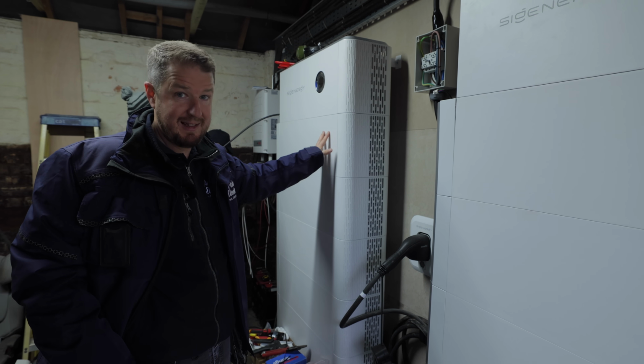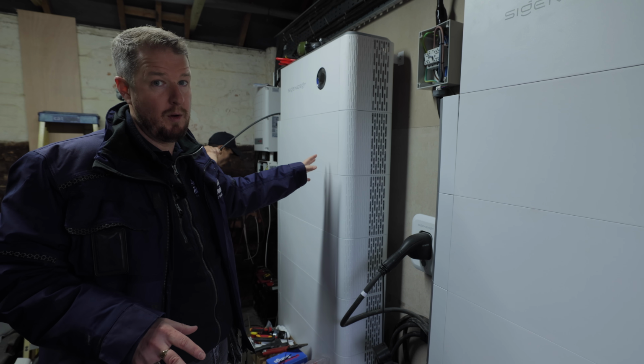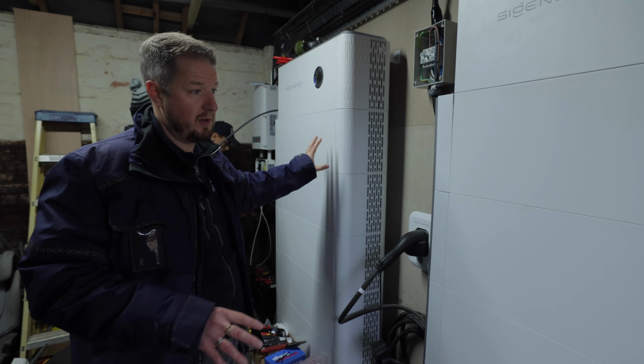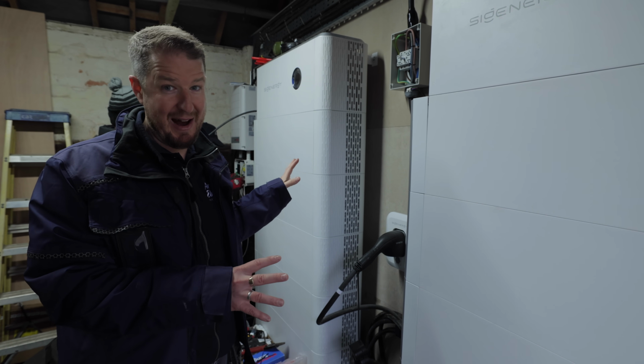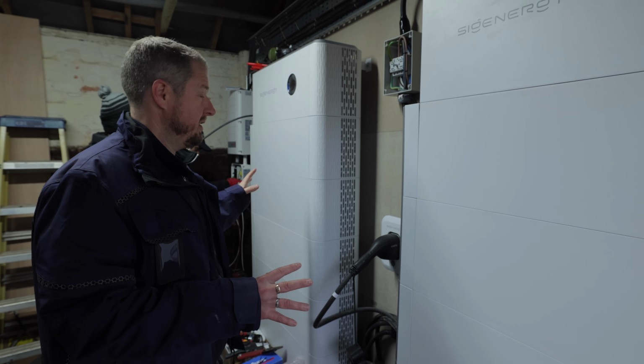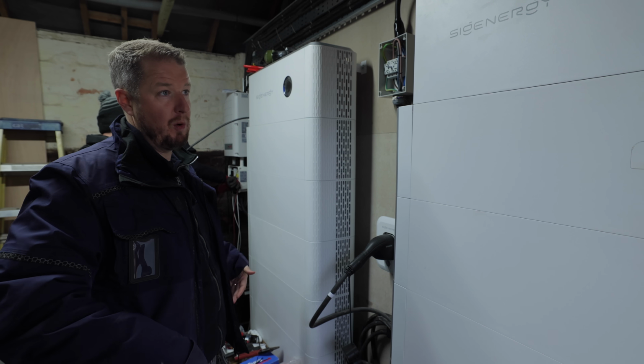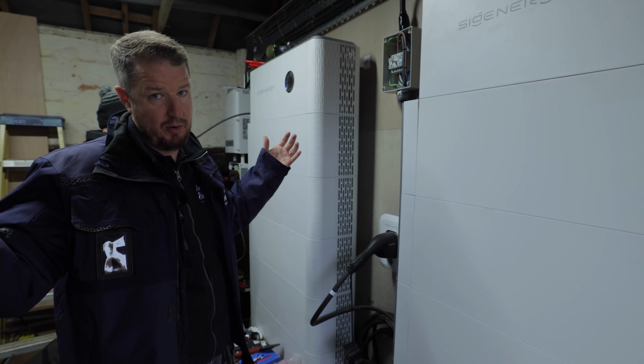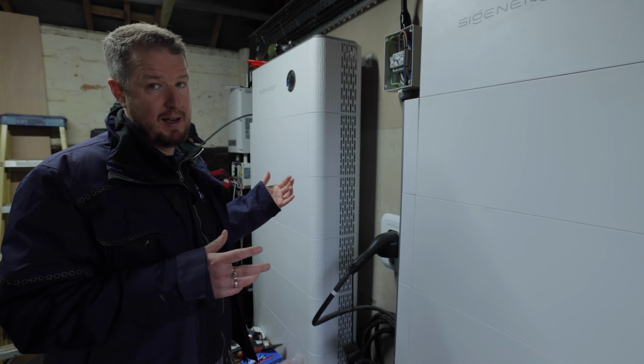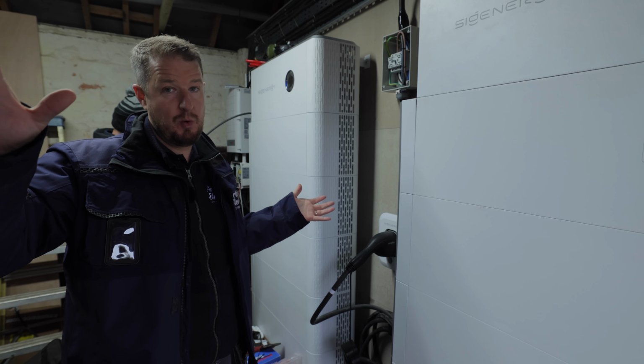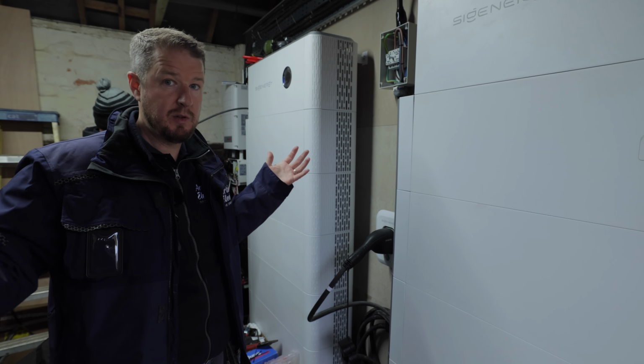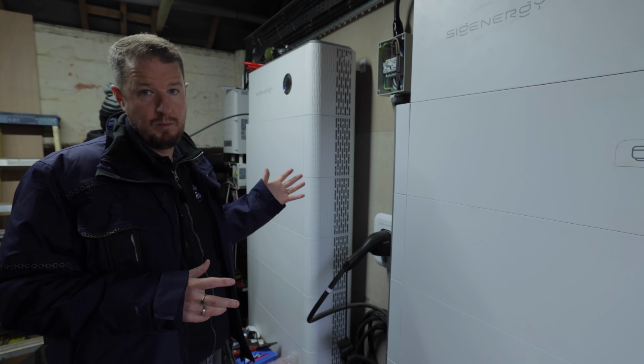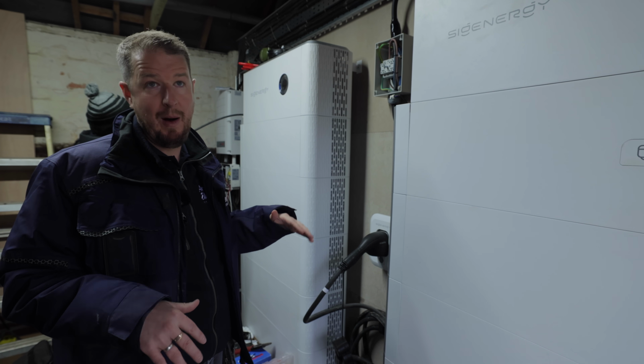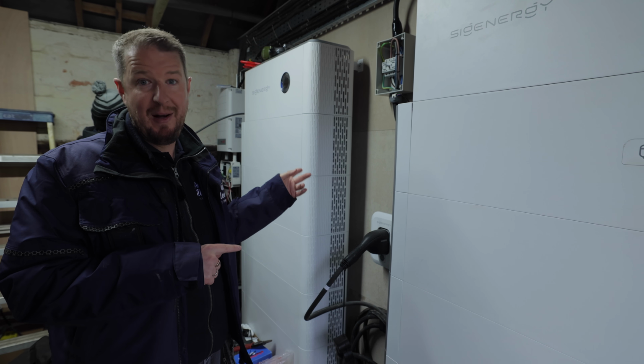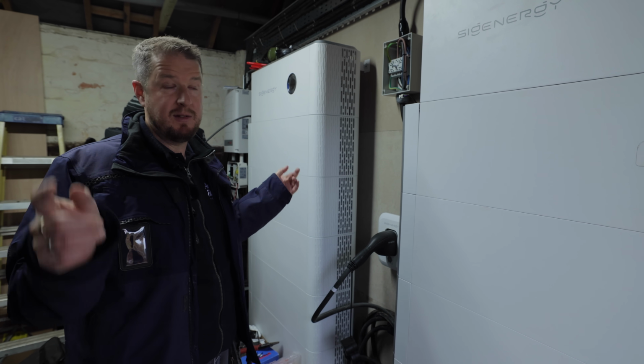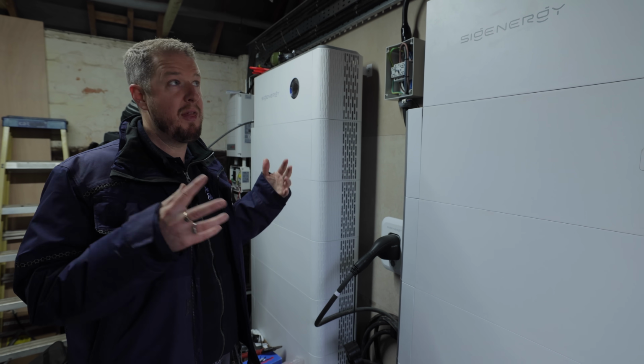And in this stack we've got 6 eight kilowatt hour modules, for a total of 48 kilowatt hours of battery storage. So across these two, we've got 88 kilowatt hours of battery storage, which, to put it into context, is enough to dump all of this power into a Tesla Model 3 and have some left over. It's enough power to run this house for about 24 hours in a grid outage, which is what the customer wanted, so that if they lose power, they're still good for 24 hours, and that's without the solar running. If it was a sunny day, the solar would be keeping these batteries topped up, and in theory they could run infinitely off grid.